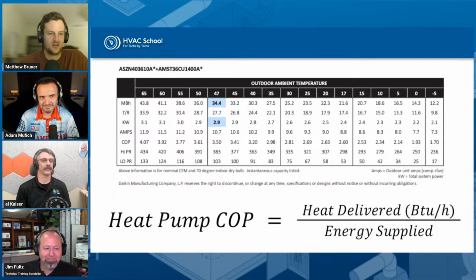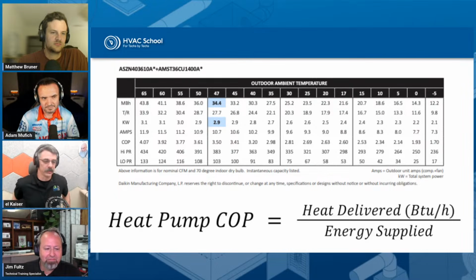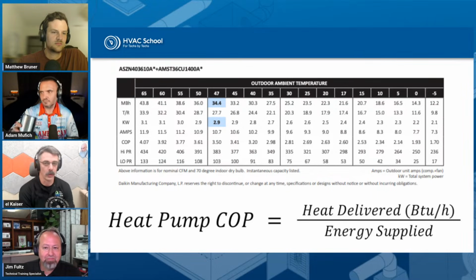So Eric or Jim, either one of you could take this one, but how are we supposed to think through that process of when that resistance heat is supposed to come on for a heat pump? Well, realistically, when we're using resistance heat, we don't want it to come on ever, if possible. We want it to come on as little as possible, because in almost all conditions the heat pump is going to be more efficient. It's got to get really, really cold outside, like serious negative Fahrenheit numbers, before we start seeing a heat pump compressor actually approach a 1 COP.